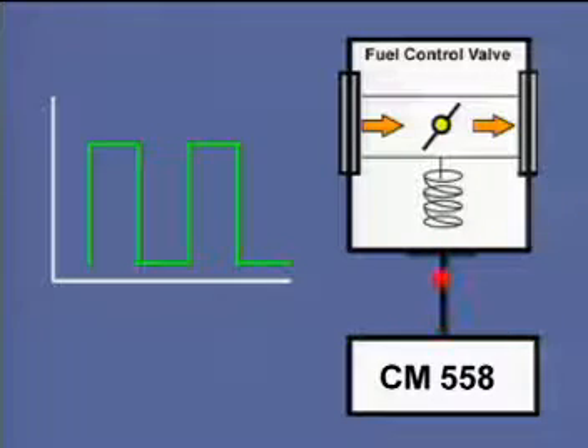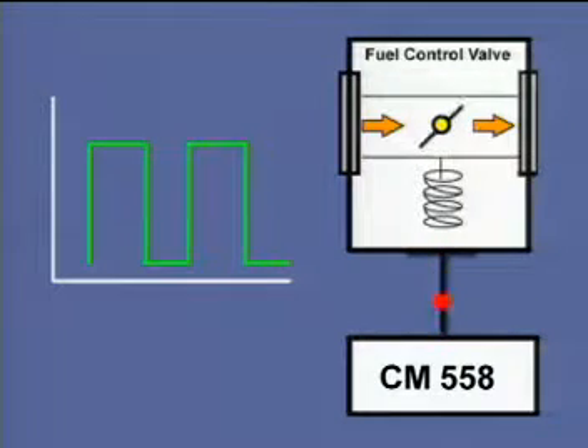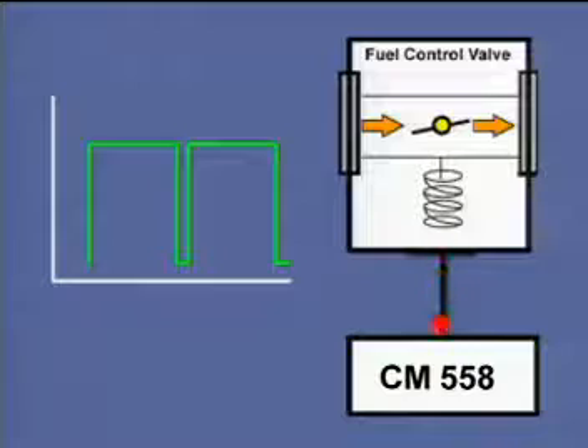The CM558 delivers a pulse-width modulated 24-volt square wave signal to the fuel control valve. The fuel control valve is a butterfly-type valve that controls the air-fuel ratio by controlling the volume of gas drawn through the gas control assembly. The fuel control valve position is fed back to the CM558. The feedback is a 0 to 5-volt DC signal.